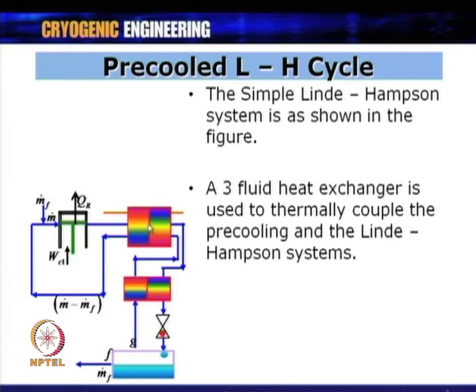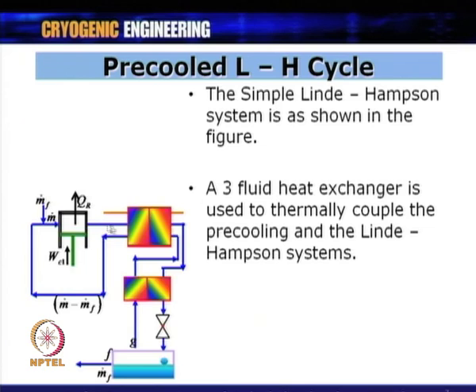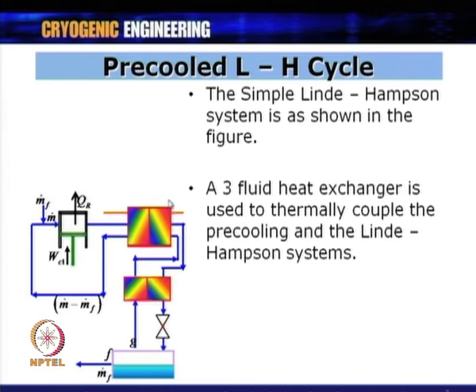This pre-cooling is achieved by a third fluid passing through the heat exchanger, making it a three-fluid heat exchanger — two fluids from the Linde-Hampson circuit plus a third fluid from the pre-cooling circuit. The three-fluid heat exchanger thermally couples the pre-cooling system and the Linde-Hampson system.